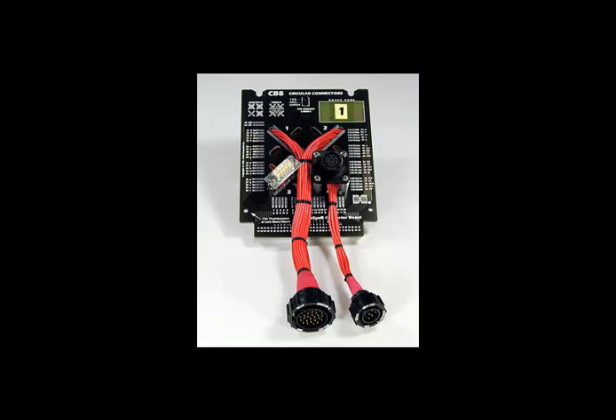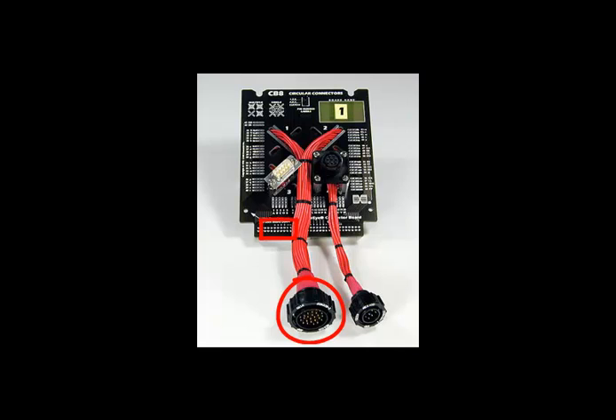Pinmaps describe the custom mating connector hardware that provides the interface between your harness or cable under test and the CableEye tester. You may have a completely custom interface directly attached to the tester. However, typically, you'll mount your mating connectors on CB boards specifically designed for this purpose, such as the CB8 board shown here. What does pinmap do, then? Briefly, it associates, or maps, the pins on your mating hardware with test points on your tester. Without such a mapping, you would only see raw test points as a result of test acquisition. With pinmap, however, you see an accurate representation of your harness or cable when viewed graphically, and the netlist contains the pin numbers from your connectors.